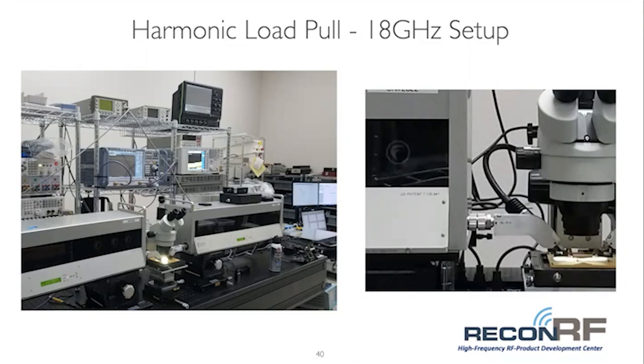This is an on-wafer setup, so there are positioners set near the device. You can see on the right a rigid airline, which is very low loss and connects the tuner directly to the device, providing low loss but very stable connection with no phase instability. So when we calibrate the tuner, we know there won't be any phase difference or shift from calibration to actual tuning.